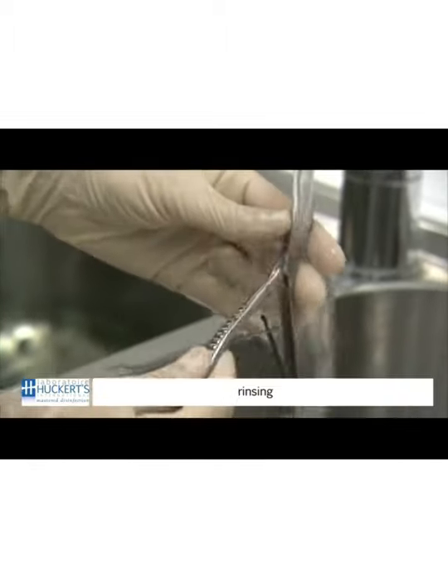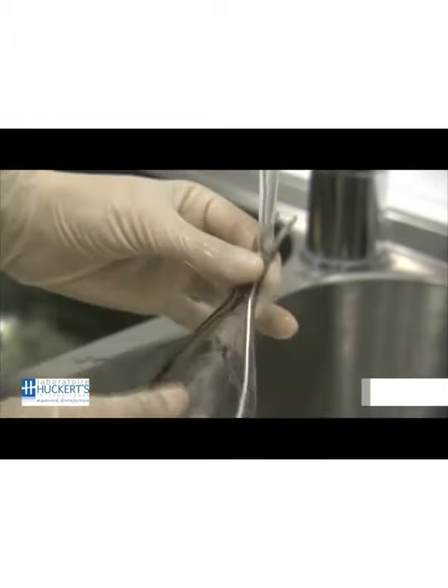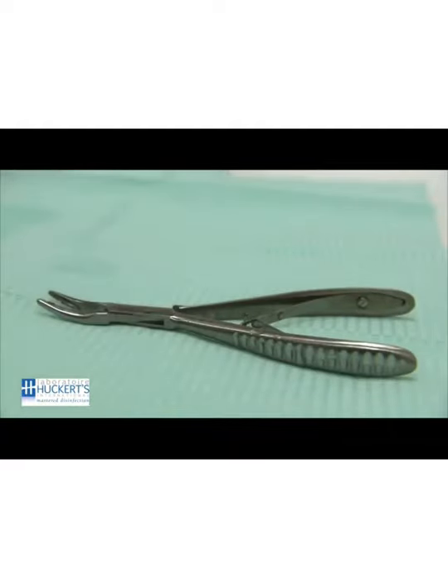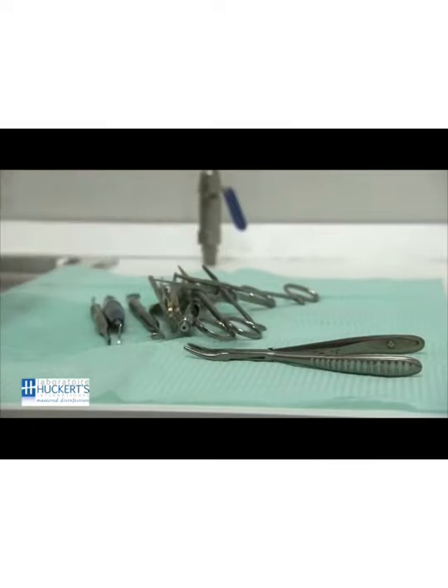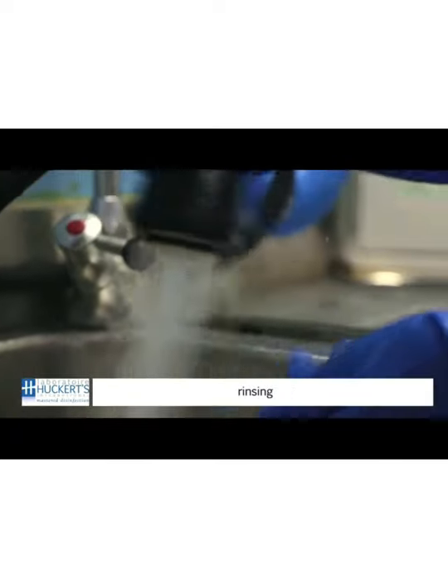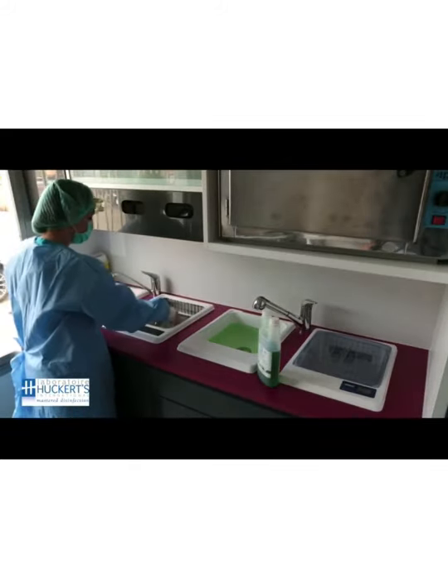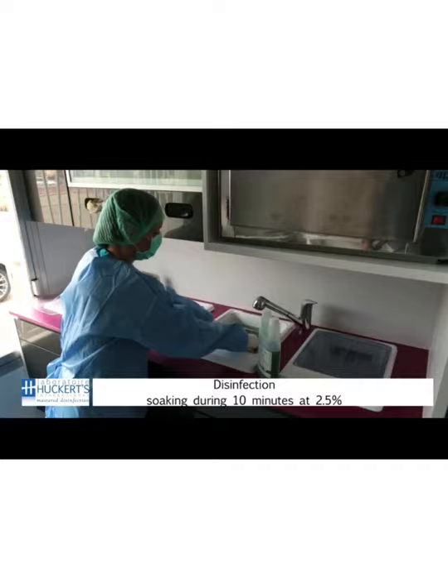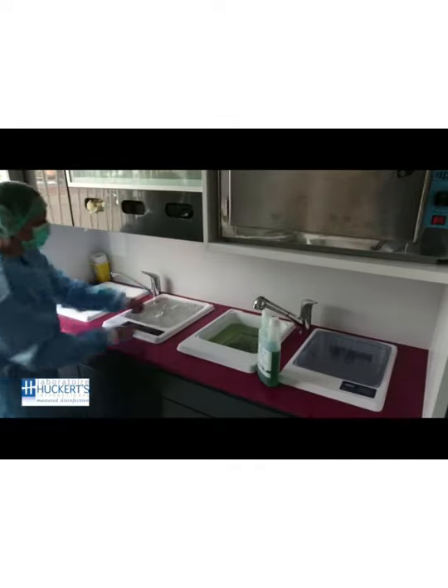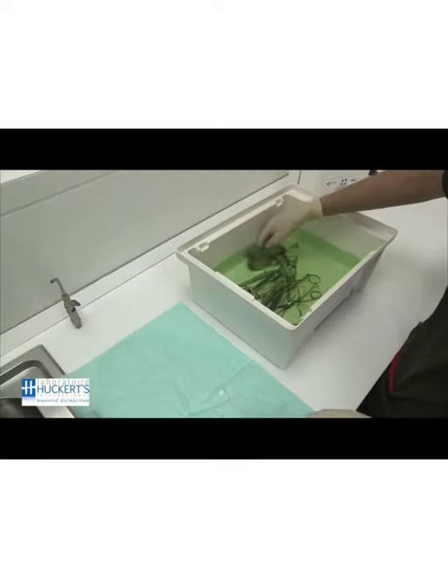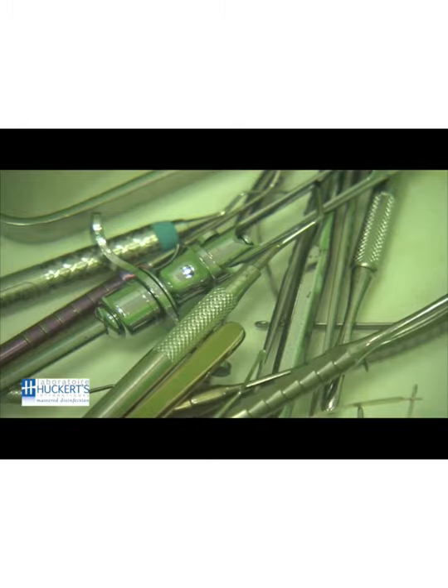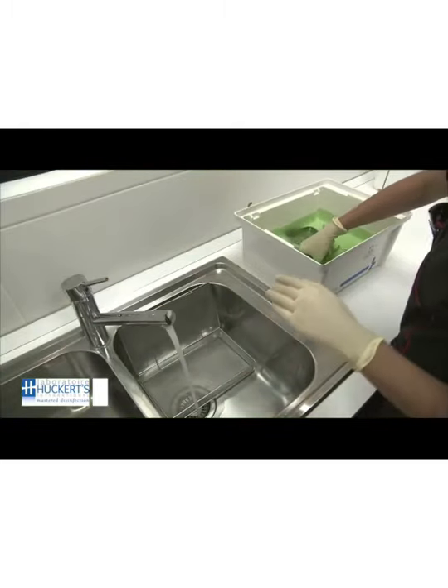Surgical instruments should be pre-soaked or rinsed to prevent drying of blood and to soften or remove blood from the instruments. For instrument cleaning, a neutral or near-neutral pH detergent solution commonly is used because such solutions generally provide the best material compatibility profile and good soil removal. The instruments are cleaned, rinsed, and washed using neutral detergent solutions, then they are soaked with disinfectant, then rinsed again and dried before putting them into the hot oven for sterilization.